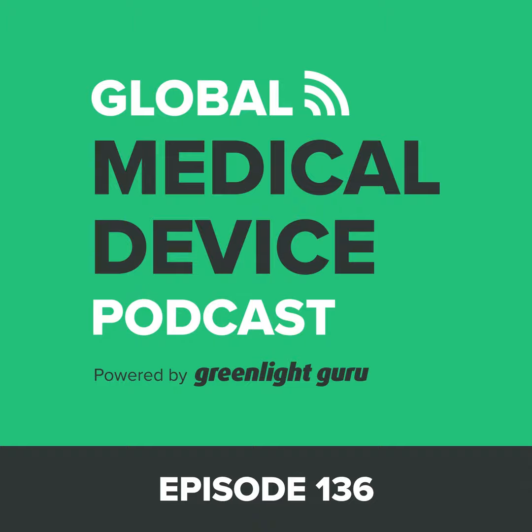So right now, you're exactly right, John. It's a pilot. FDA is looking for 9 companies to volunteer, or victims perhaps, that represent a very broad swatch of the medical device industry. They need to be planning to submit at least one 510K within the first 3 months. And the company also needs to agree to provide feedback to the FDA on the eSTAR process.